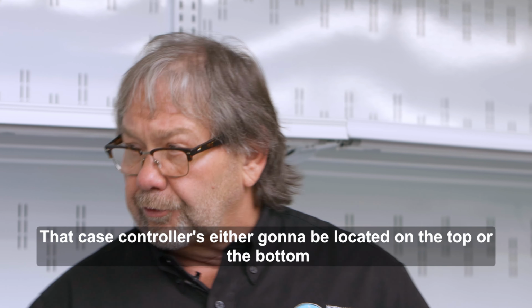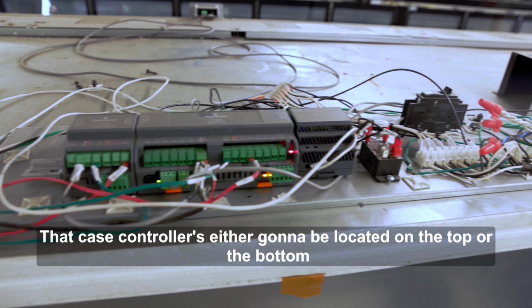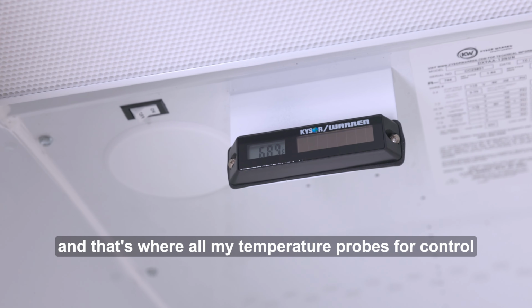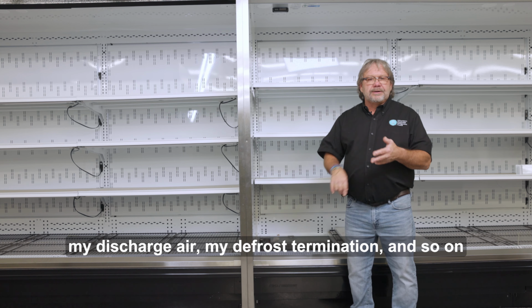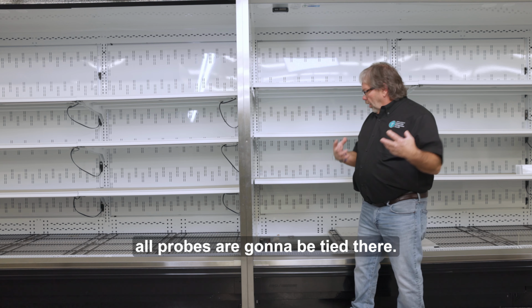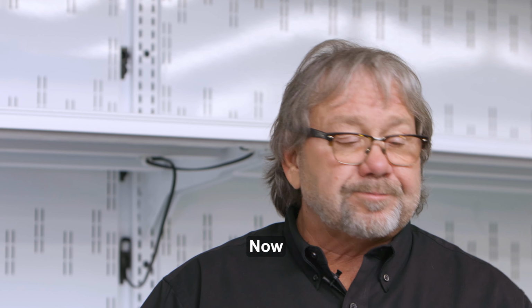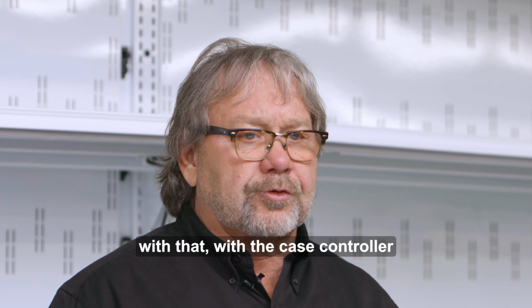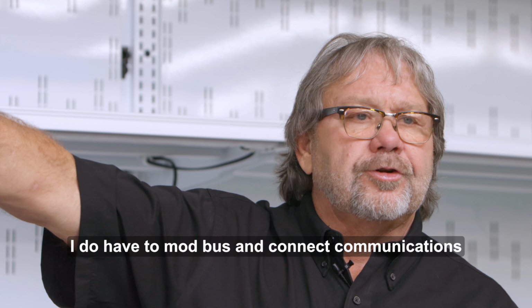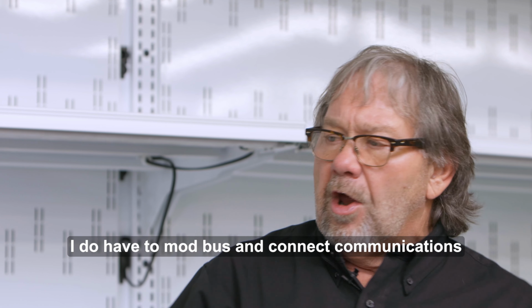And then the other thing, in order to have an electronic expansion valve, I have to have a case controller. That case controller is either going to be located on the top or the bottom, and that's where all my temperature probes for control, my discharge air, my defrost termination, and so on, all probes are going to be tied there.